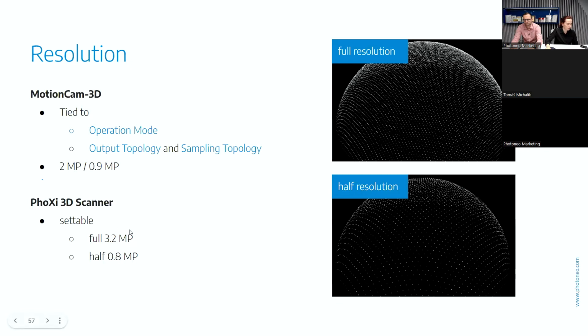On the PhoXi 3D scanner, we can set whether we want to use half resolution or full resolution. The full resolution is 3.2 megapixels and the half resolution is 0.8 megapixels. The advantage of the half resolution is that the computation is done very fast because there are so many fewer 3D points. So it takes a lot less time to compute the 3D points, and it also takes a lot less time to transfer it to PhoXi Control. And the difference is apparent.